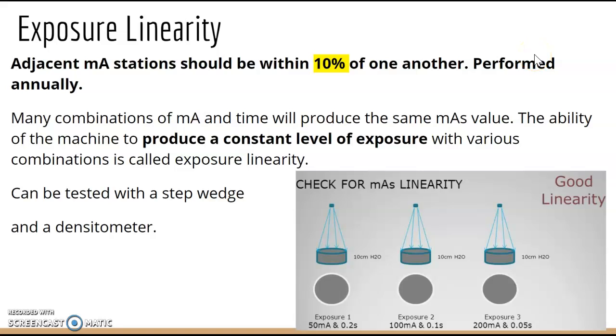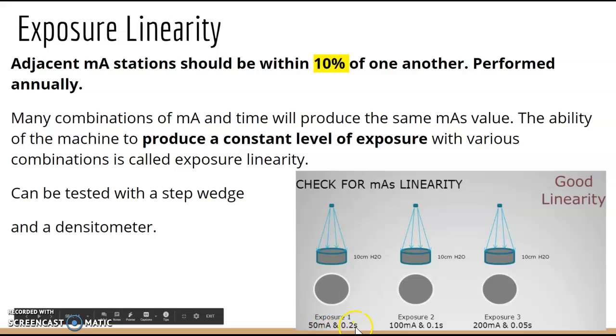Exposure linearity means adjacent mA stations should be within 10% of one another; this is tested annually. It tests the machine's ability to produce a constant level of exposure even when varying mA and time combinations. It can be tested with a step wedge and densitometer.